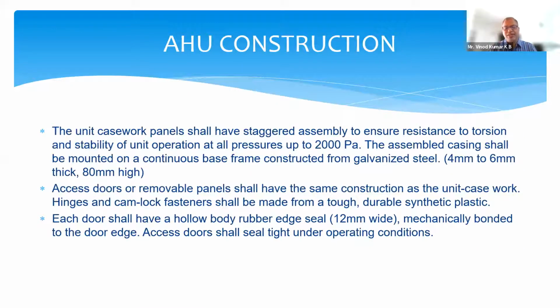Now, the AHUs have a big fan or blower inside them, and it's pushing the air into your theater or the ICU. So there's a lot of pressure happening. So the equipment manufacturer has to make sure that the AHU panels don't crack in or crack outside because of the pressure. The panel construction of the AHU should be able to maintain a pressure up to 2000 Pascal, and the framework of the AHU should be strong enough, with a minimum thickness of 4 mm to 6 mm, and the height of the frame around the base of the AHU should be 80 millimeters.